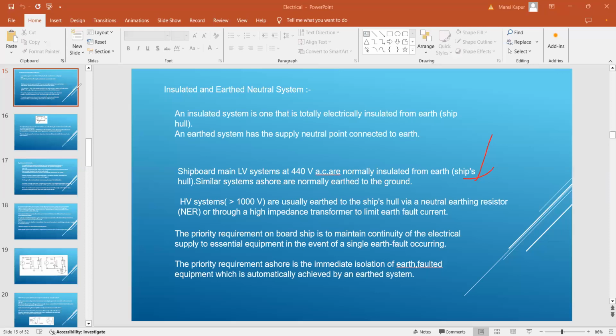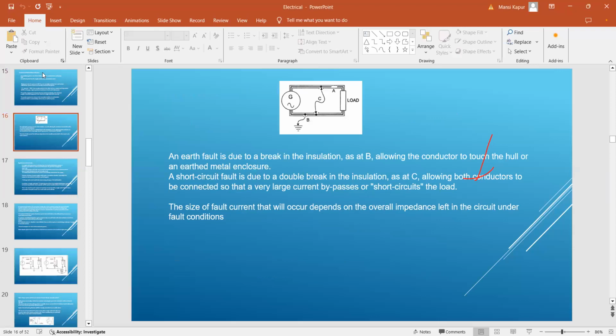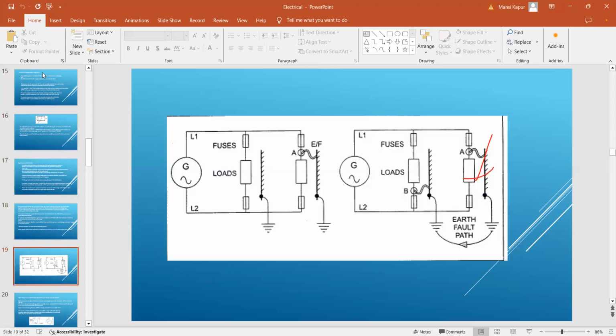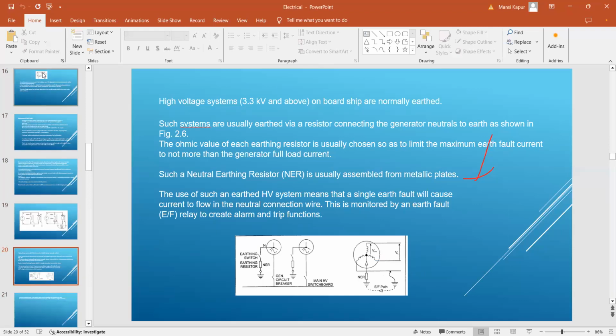Obviously, we are doing this in the high voltage system because humans are also there, and if a human touches something and there is a potential difference, the human can get a severe shock. That is the reason, and we are going to see how they maintain the supply to the essential equipment. So high voltage systems, like your 3.3 kV or above, or 1.1 kV or above, on board the ship are normally earthed. Can you see here? They have put the neutral earthing resistor and earthed the system.